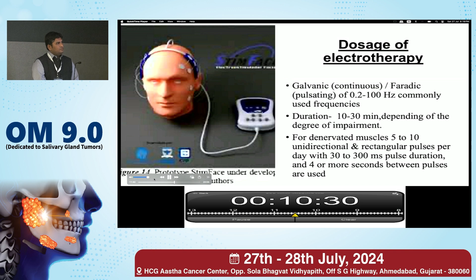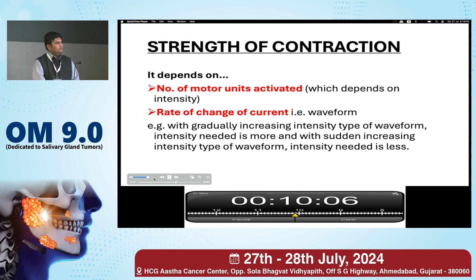Strength of contraction. Strength of contraction depends on two factors. One, number of motor units activated, which in turn depends on the intensity. Second, rate of change of current, that is the waveform. Example, with a gradually increasing intensity type of waveform, intensity needed is more, and with a sudden increasing intensity type of waveform, intensity needed is less.